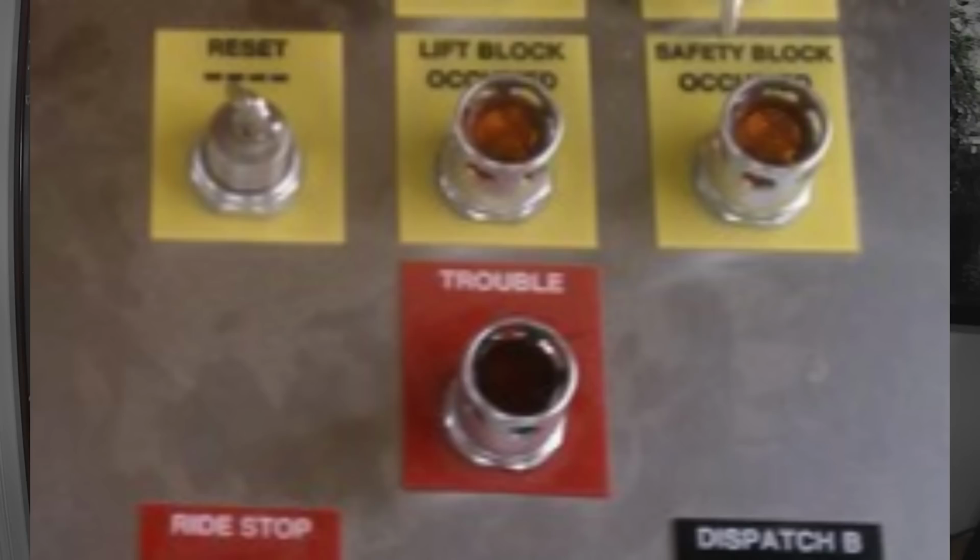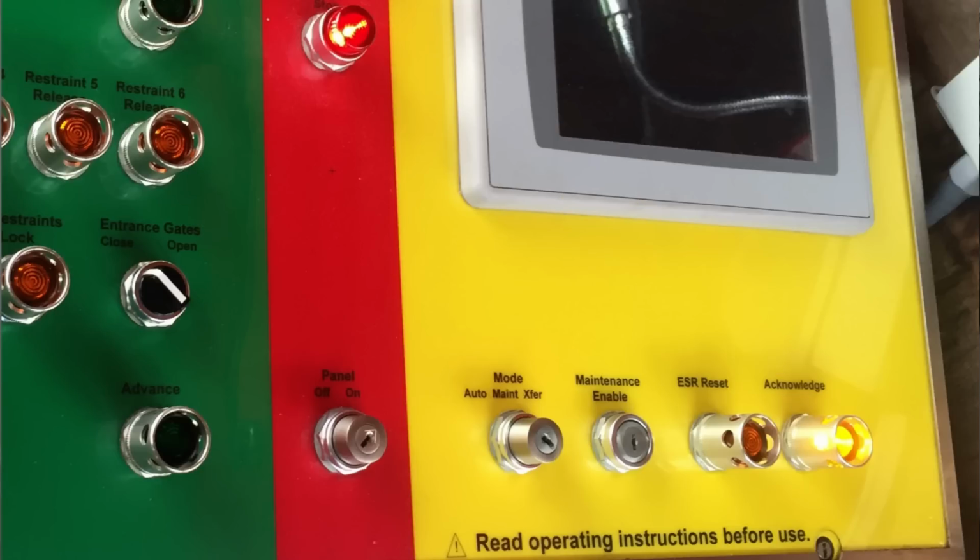Manual mode is also used for resetting faults. Like typically when you have a fault, you can't reset it in automatic. You have to go into manual mode to reset the fault. Faults occur when a piece of equipment doesn't behave the way they thought it should behave. Then it produces a fault. So we'll use one of our brakes, for example. Let's use a slow acting brake, which is very common.